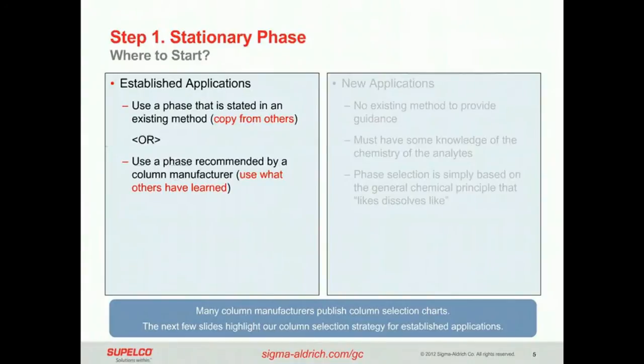So we need to choose the stationary phase, and where do we begin? There are really two strategies for stationary phase. One is established applications where somebody has done something before that you may be able to copy. The other is new applications where you're developing an application for analytes that have never been tried by GC before. We'll discuss both paths.